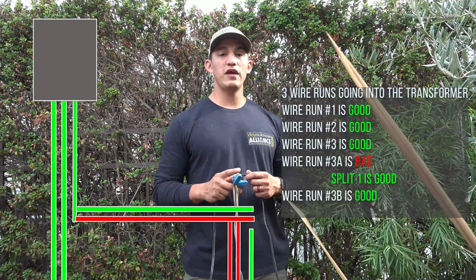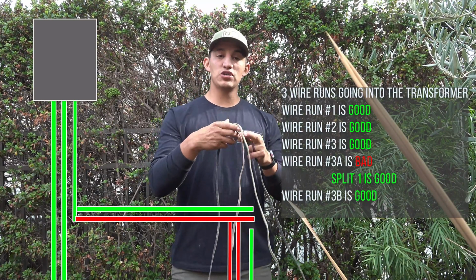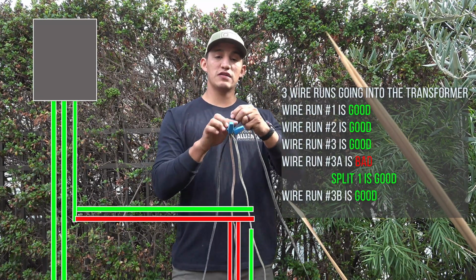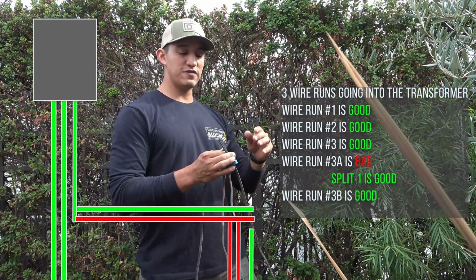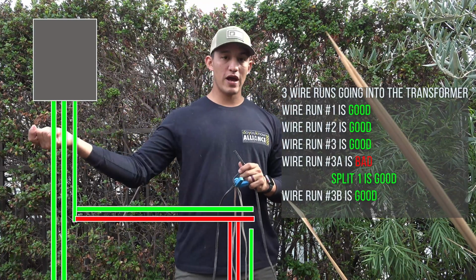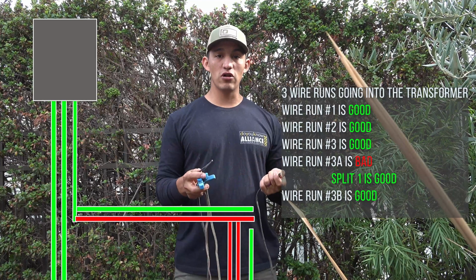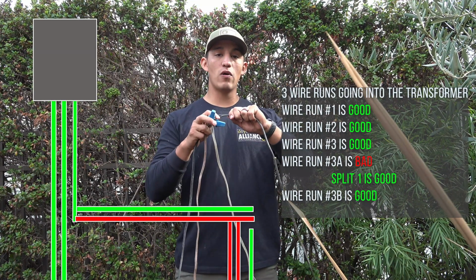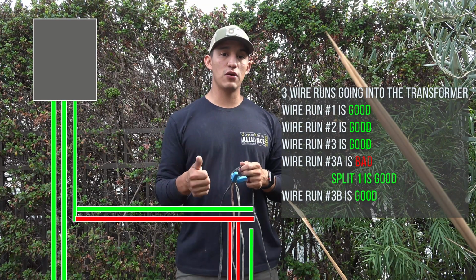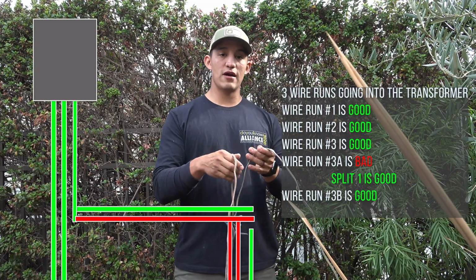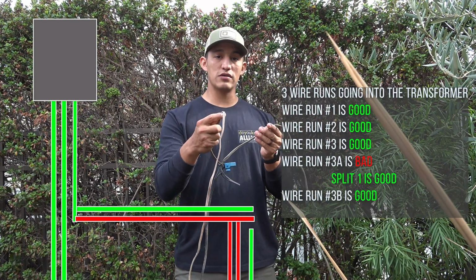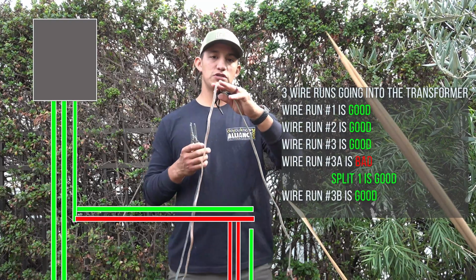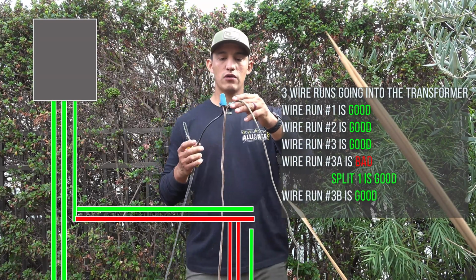Here's an update. At this junction, we ended up cutting the black wire that ran along the fence. We turned the transformer back on and there was a fault light, which tells us that black wire is actually fine. It also narrows it down to one of these brown wires being the real issue. We're left with two brown wires trying to find our short.